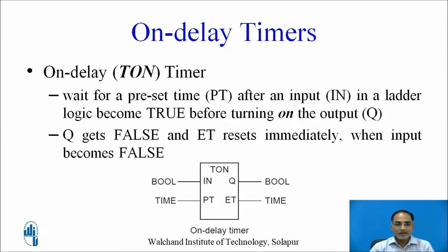On-delay timers wait for a preset time defined by the PT value after an input in a ladder logic becomes true, before turning on the output Q. Q then gets false and ET resets immediately when the input becomes false.